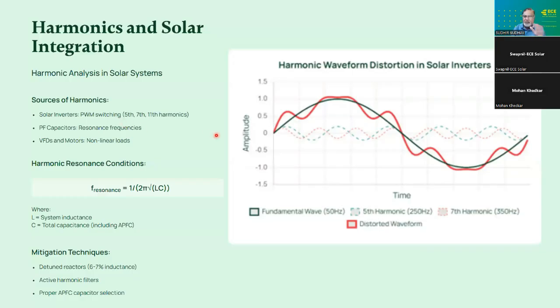Now, let's ignore the 11th harmonic, as the effects are not so high. But if you consider the 5th and 7th harmonics, the dark red line is the resultant of the 5th and 7th harmonics, which is introduced in the system by solar itself. The situation becomes complex if there are fixed capacitors or APFC installed in the premises where solar is getting installed, because it can form a resonance condition if the capacitive impedance equals the system's inductive impedance.